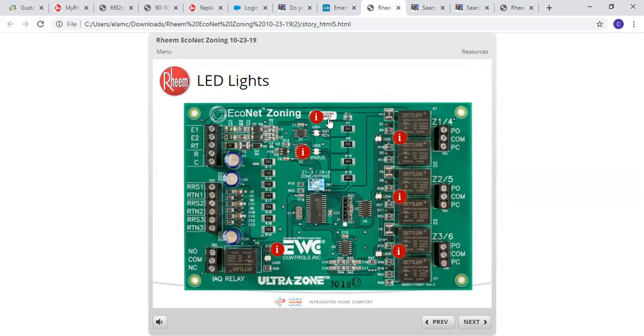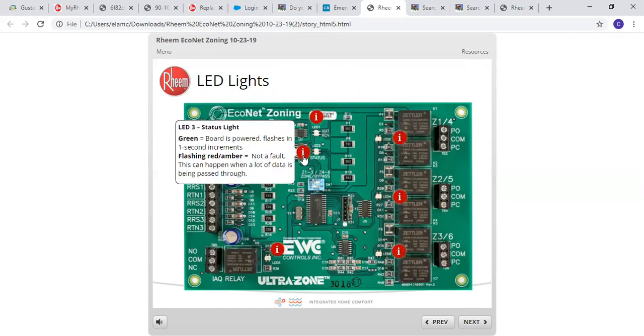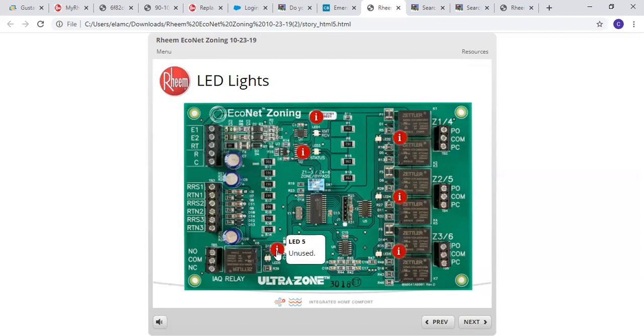So we'll go over some LEDs here on the board. The first one, the top one here, is the LED transmit and receive. Random blinking indicates serial bus communication. This LED here tells you green, board is powered, flashing in 1 second increments. The flashing red or amber is not a fault. This can happen when a lot of data is being passed through the board. Come down to the LED here. This is unused.